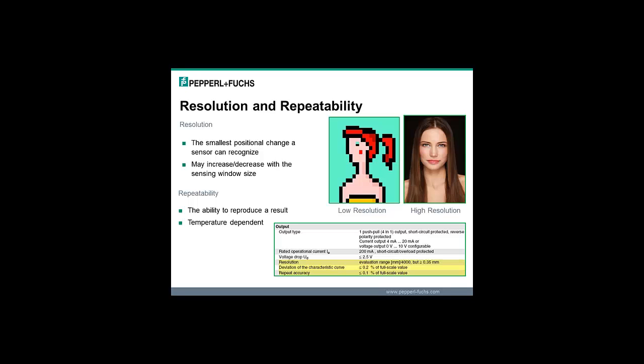The next 2 concepts to discuss with ultrasonics as far as components of accuracy are the resolution and the repeatability. Resolution defines the smallest positional change that a sensor could recognize. So you can see on the 2 graphics on the right, for low resolution, you get a very blocky image. And that same kind of concept applies to an ultrasonic sensor, where maybe if you have an analog output that is 4 to 20 milliamps, if you have a 1 milliamp resolution, you would go 4 milliamps, and it would jump up to 5, and then 5 jumps up to 6. If you have a higher resolution, then you can go 4 to 4.1, 4.1 to 4.2, 4.2 to 4.3, etc. So that's the difference in resolution.